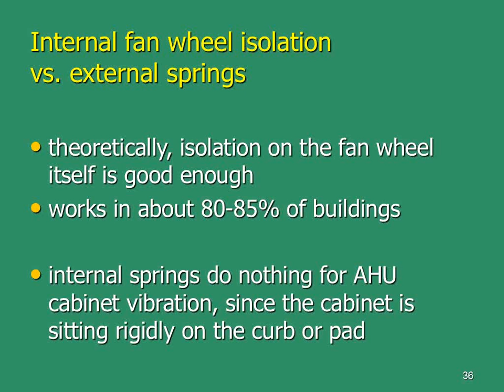I'm the first guy to say that 80 or 85% of the buildings out there don't have significant noise problems. But if you're one of the unlucky 15%, it's real ugly to try and fix. So if it's just your typical run-of-the-mill office building or warehouse, I don't get too excited. But if you talk about putting an air handler over a classroom, like that earlier question, a training room or a conference room, over an auditorium, I'm going to dig in my heels and say, you really need to not use the internal isolation on the fan wheel. You need to put the whole unit on springs.